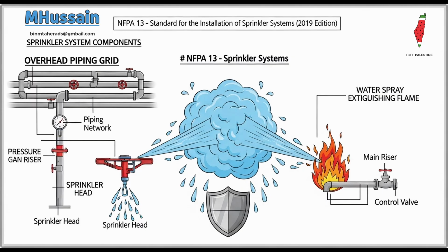Furthermore, in areas that are subject to freezing temperatures, the piping between that check valve and the outside coupling must be equipped with an approved automatic drain valve. This prevents water from getting trapped, freezing, and damaging the connection when it's not in use. Okay, this is where NFPA 13 really dives into the deep end of prescriptive engineering, warehouse storage. It's arguably the ultimate fire challenge, requiring engineers to classify the fuel load, the commodity, with extreme precision.